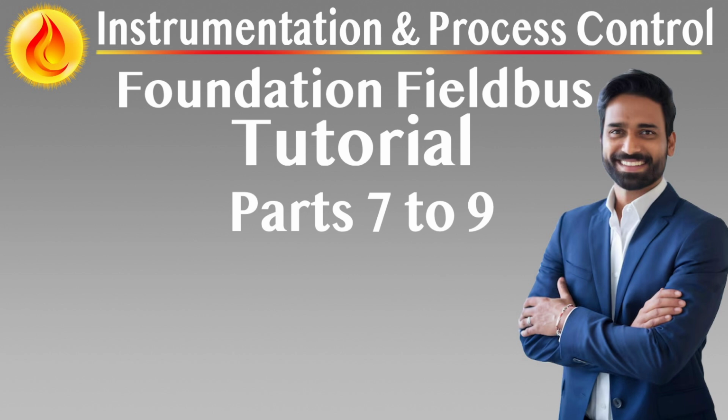HSE conforms to standard IEEE 802.3 Ethernet and IP protocols, allowing seamless interconnection with commercial networking infrastructure while preserving the deterministic behavior and object-oriented architecture of Foundation Fieldbus. Unlike H1 segments that connect low-speed field devices using a single twisted pair, HSE supports switched full duplex communication between control systems, H1 interface modules, and HSE devices via high-speed Ethernet links, typically using Cat6 or fiber optic cabling.